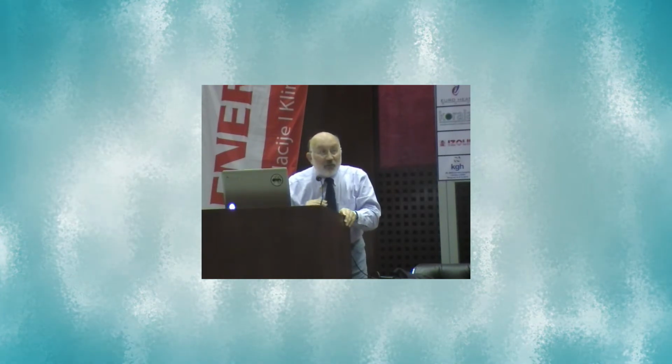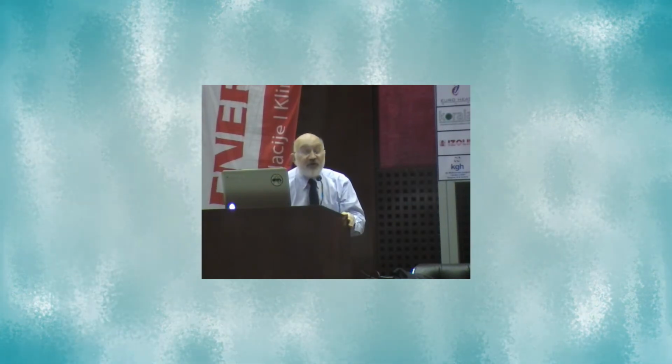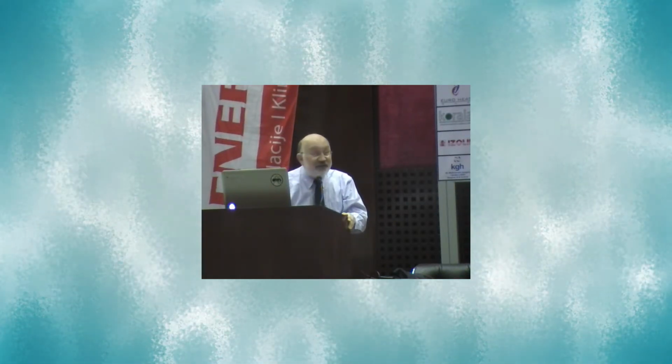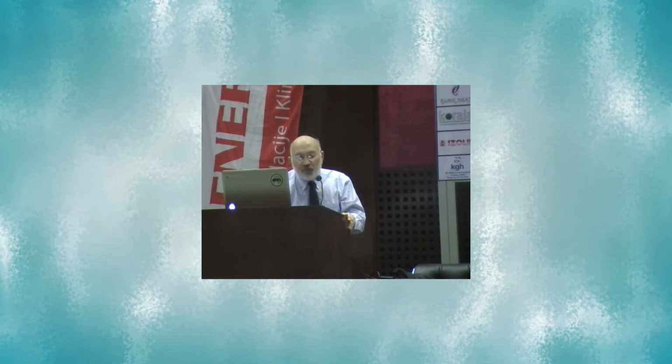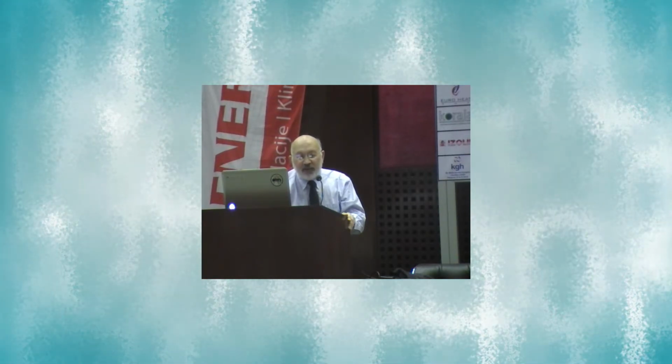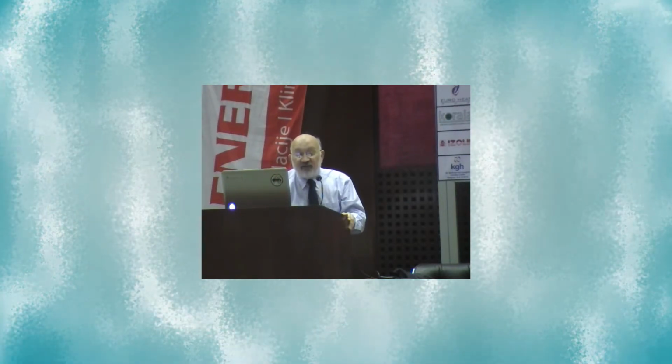What is the most interesting is the location of the link between these two things. And that is at the wall of the tank, and this is schematically presenting a tube of the condenser. So this tube of the condenser brings hot refrigerant, and that heat, that energy, will be transferred to water here at this wall. So this is in a cross section, so this here is that condenser tube, water being heated on this wall is going up, and basically we have presented this as a fin.